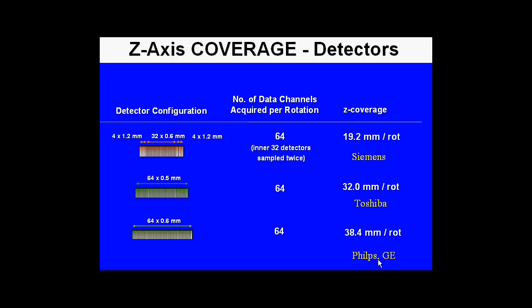This shows the z-axis coverage of the detectors for each of the major manufacturers: Siemens, Toshiba, Philips, and General Electric. The Siemens scanner is a 64-slice scanner that actually uses 32 rows of detectors which are sampled twice. The coverage is 19.2 millimeters per 32 multiplied by two, producing 64 slices. The Toshiba, Philips, and GE are true 64-slice scanners.